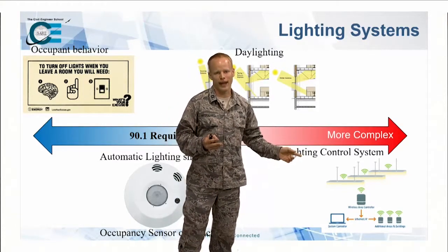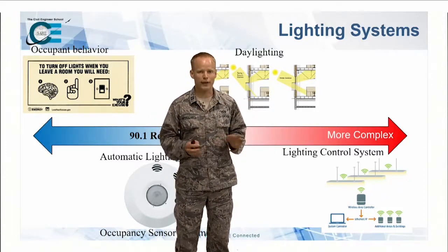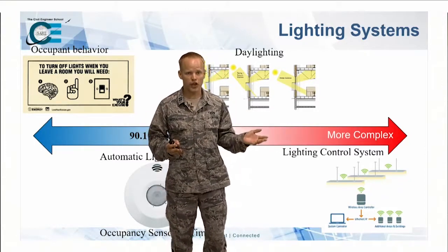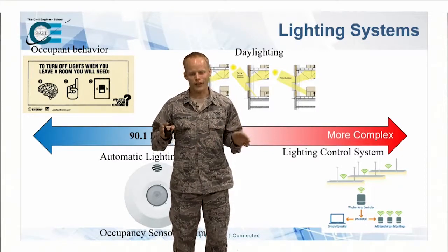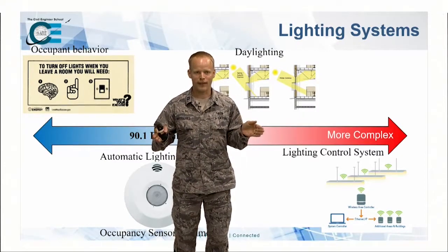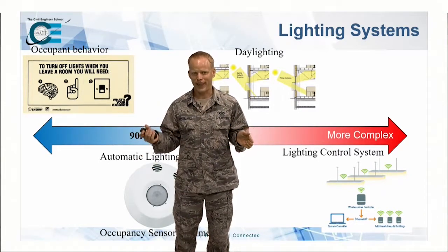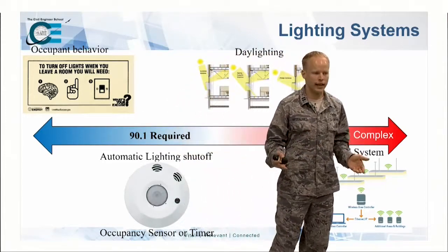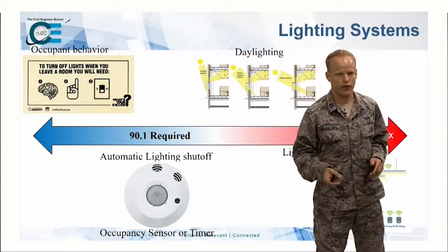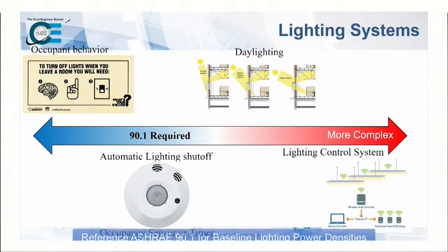And then you integrate that with a daylighting sensor or a lighting control system. At NREL they had these, and they worked pretty good, except they could have worked better. The lights would suddenly be very bright, and then the daylighting sensor would say, hey, you have plenty of light, and they would turn off. But they'd turn off like that. So it got kind of distracting. But in the end, you save energy. You take advantage of that energy from daylighting.